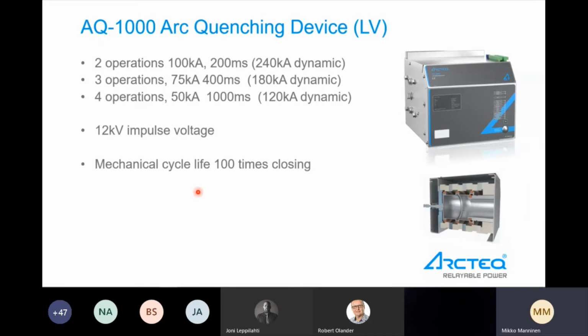And here are some values. This device AQ1000 has been tested up to 100 kiloamps, and quite a typical low voltage application is around 50 kiloamps. But actually, low voltage boards are getting higher and higher values all the time, mainly because of the hybrid technology. 50 kiloamps is quite standard, but there have also already been 100 kiloamps systems. But AQ1000 has been tested with 100 kiloamps.